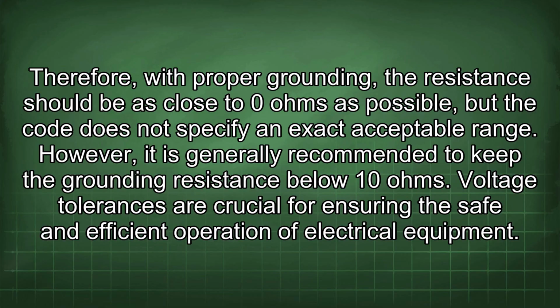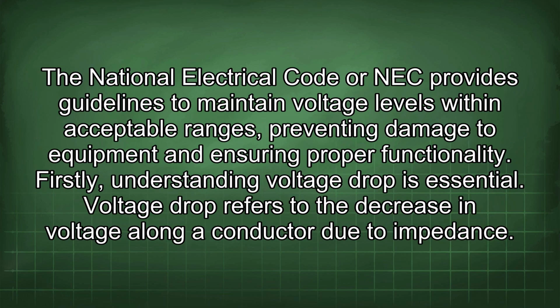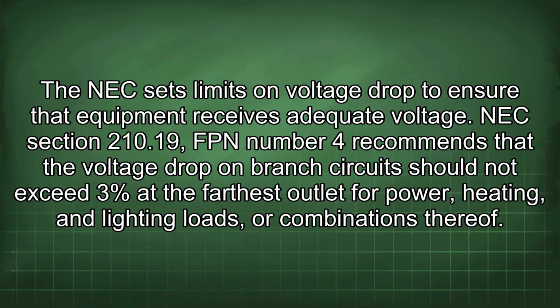Voltage tolerances are crucial for ensuring the safe and efficient operation of electrical equipment. The National Electrical Code or NEC provides guidelines to maintain voltage levels within acceptable ranges, preventing damage to equipment and ensuring proper functionality. Firstly, understanding voltage drop is essential. Voltage drop refers to the decrease in voltage along a conductor due to impedance. The NEC sets limits on voltage drop to ensure that equipment receives adequate voltage.